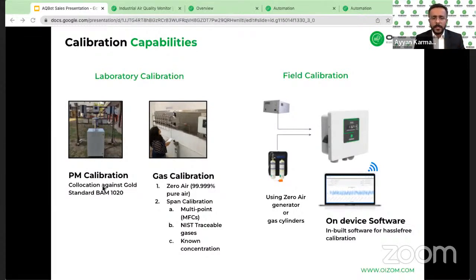The particulate matter sensors are co-located against a reference system, the Met One BAM 1020—a globally accepted gold standard for particulate matter measurement. Every AQBot is dispatched with a calibration certificate by a NABL or ISO IEC 17025 accredited laboratory. So this is the part where laboratory calibration is done: there's a pre-check, a post-check, and then we take the devices out of the facility.